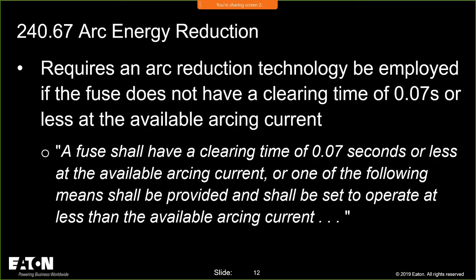Okay, so 240.67 tells us that we're required to have an arc reduction technology employed if the fuse doesn't have a clearing time of 0.07 seconds or less at the available arcing current. So now there's a term, arcing current. Arcing current is not defined in the National Electrical Code. Public input, hint. There's no definition of that.